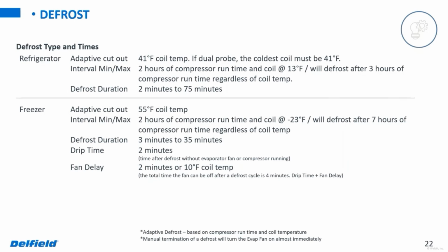So maybe we don't hit that defrost at the 2 hour mark, or even a 3, 4, 5, and 6 hour mark, but eventually we get to 7 hours, we'll go through a defrost then. So the defrost duration, again, like we mentioned previously, is a little bit different here for the freezer than the cooler. We're looking for a 3-minute minimum up to 35, and then we're going to be terminating at the 55-degree coil temp.